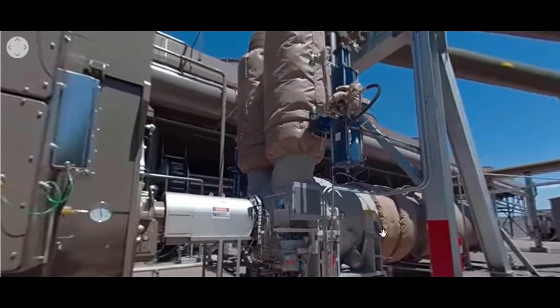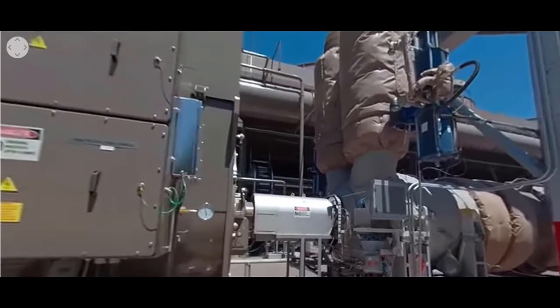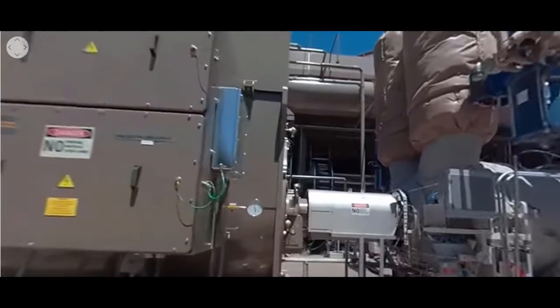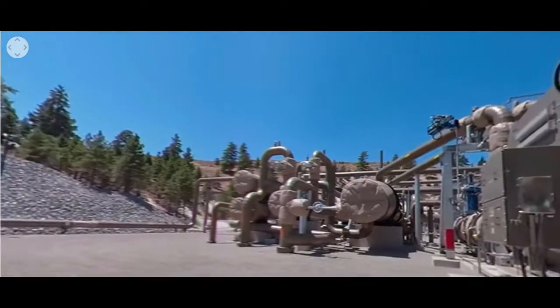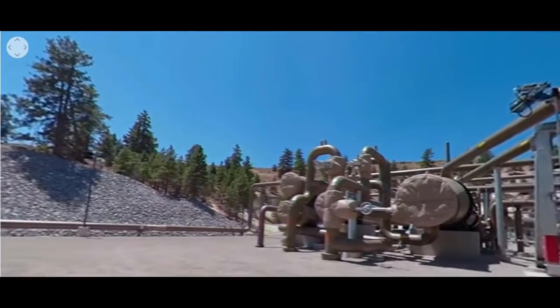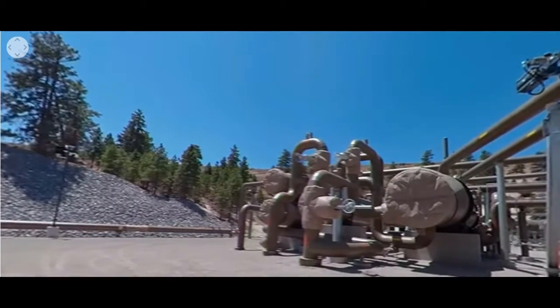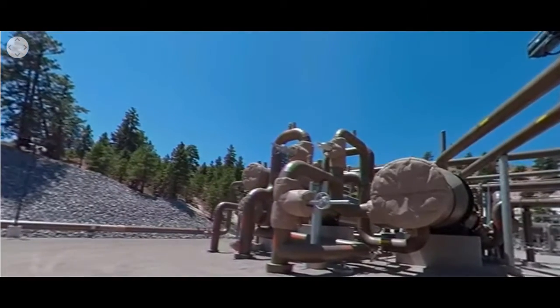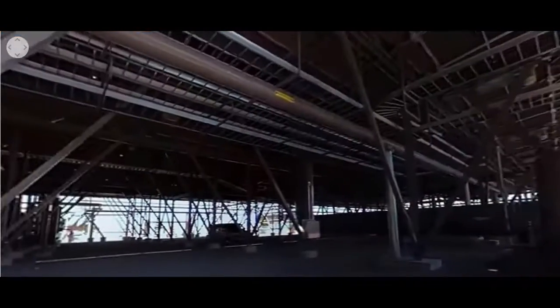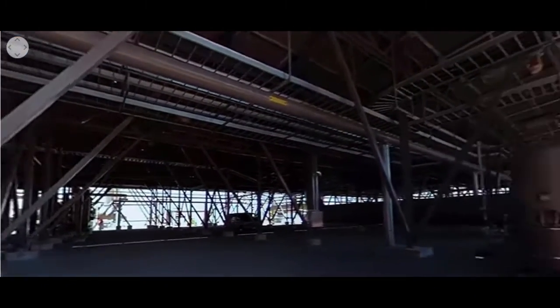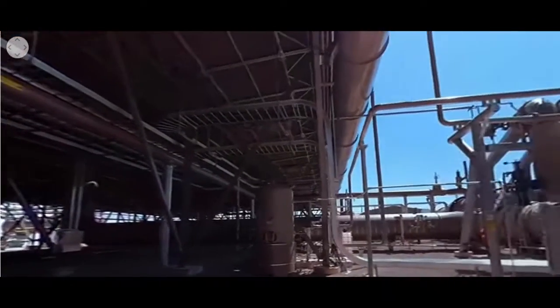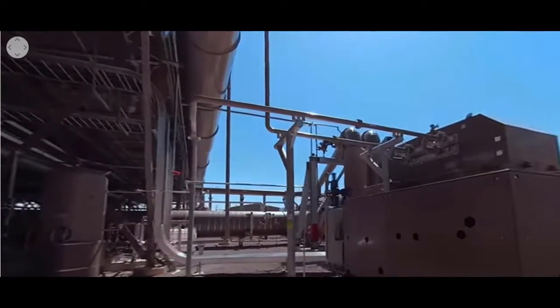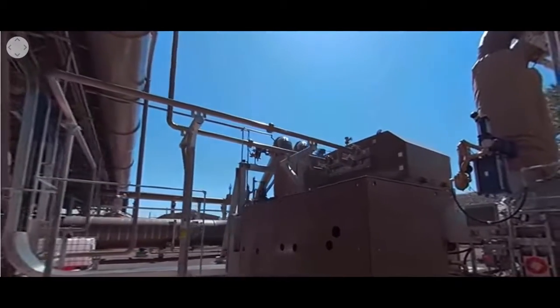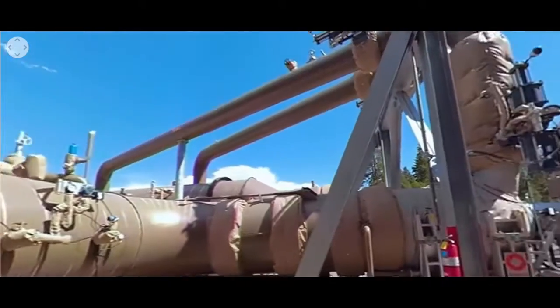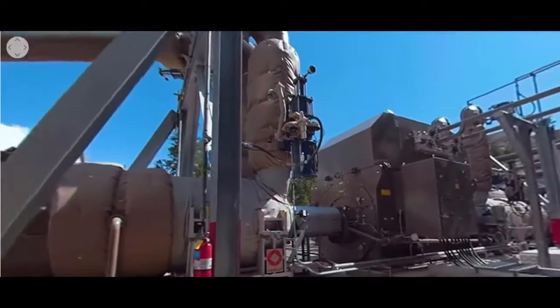I mentioned that the turbine rotates by the force of vapor, but where does that vapor come from? This is what is known as a heat exchanger. Geothermal brine, approximately 300 degrees Fahrenheit at this site, is piped from the reservoir to the heat exchanger, where the brine heats a separate working fluid to a vapor. The beauty of the heat exchanger is that the geothermal brine never comes into contact with the working fluid or with the turbine.